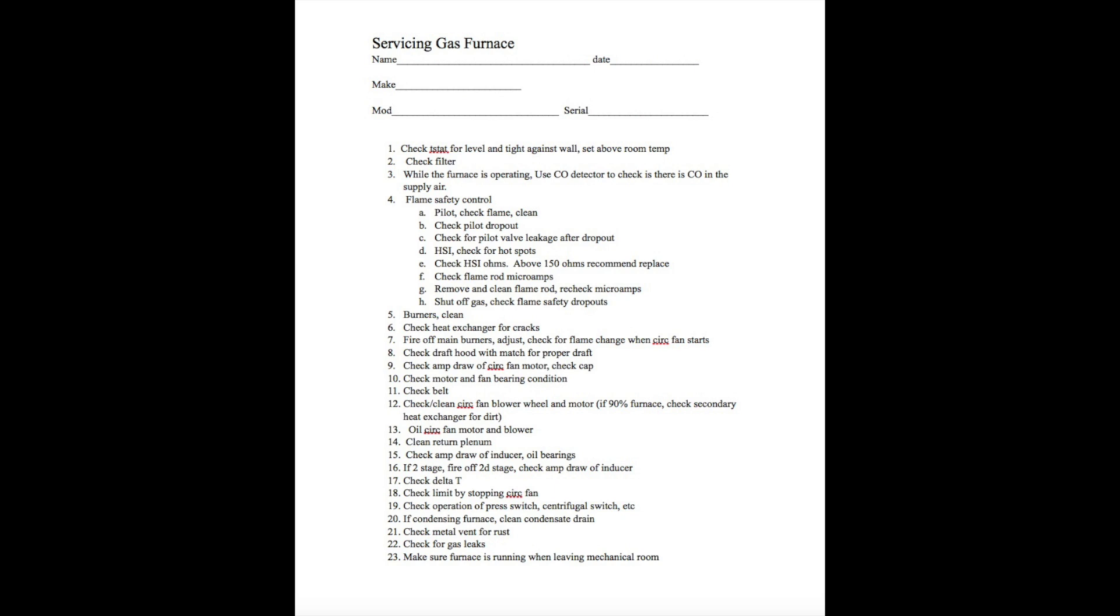Check the belt. If it's a belt drive, pull the belt off. Be sure it's in good condition and be sure it's as tight as it should be.